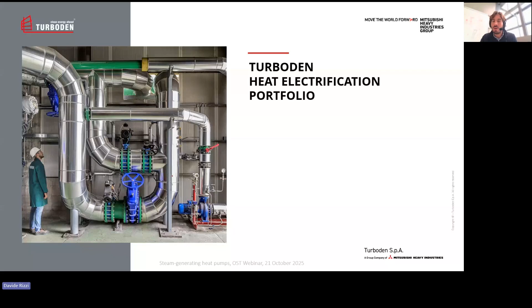Moving to our heat pump portfolio, you can see from this slide that, as I mentioned before, we have 2 main technologies: the heat pump and the MVR, referred here as LHP and MVR - just the acronyms. In terms of area of application and sizes where we work, looking at the graph on the top right, we can see that we can propose solutions from 5 megawatts of thermal power discharged at the condenser, up to 50-55 megawatts per single frame.